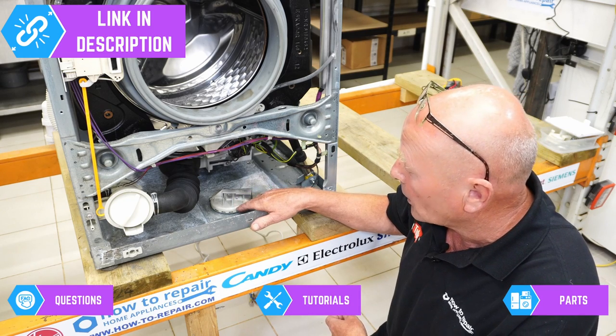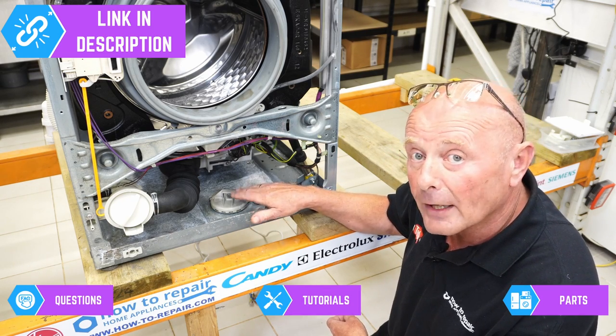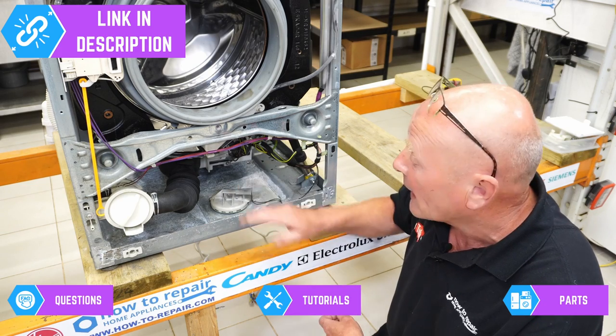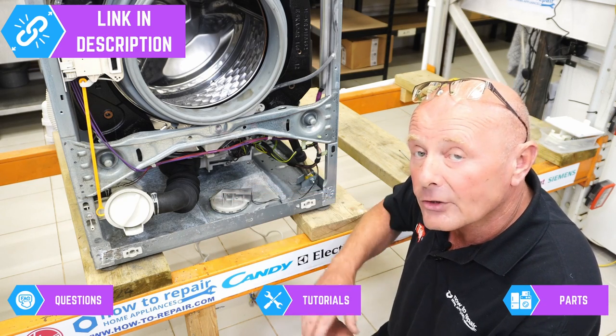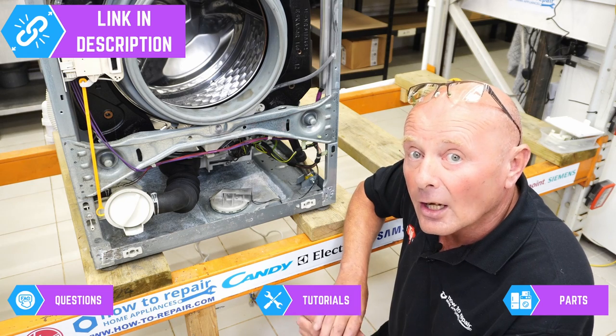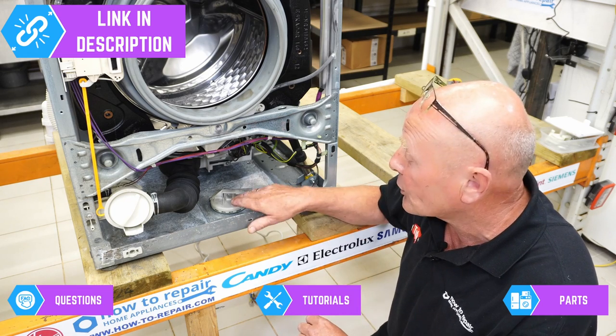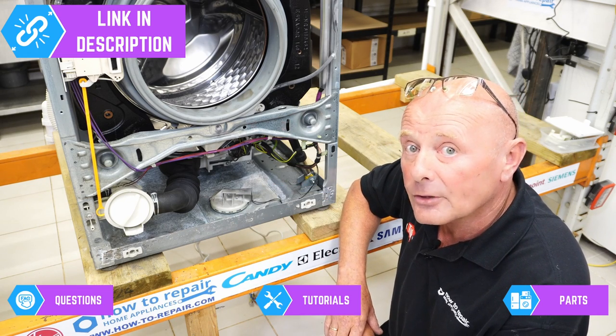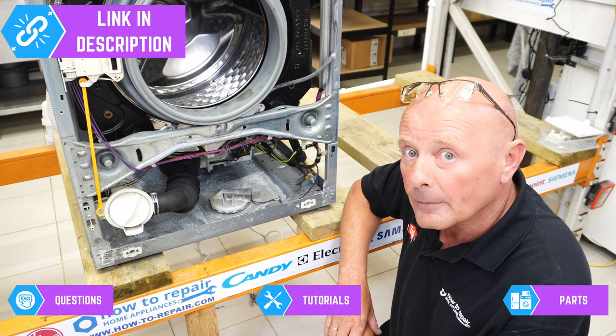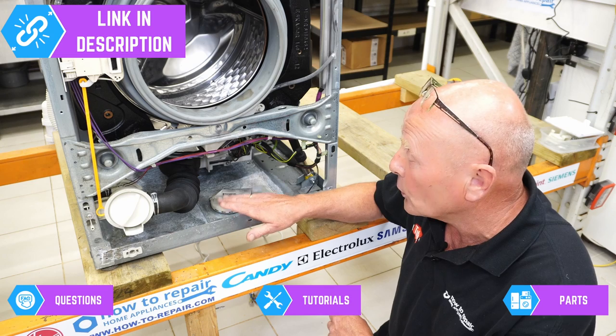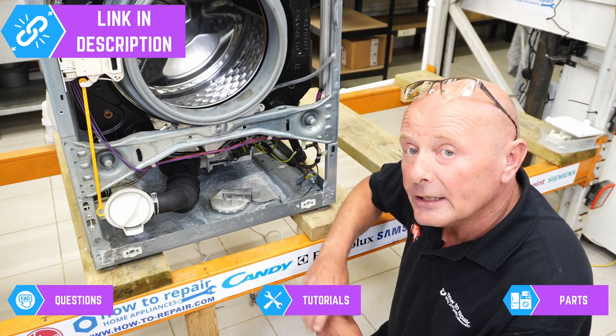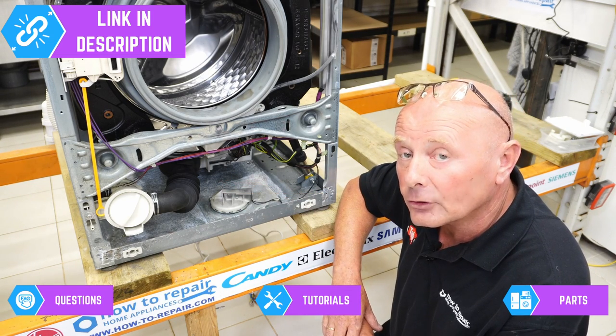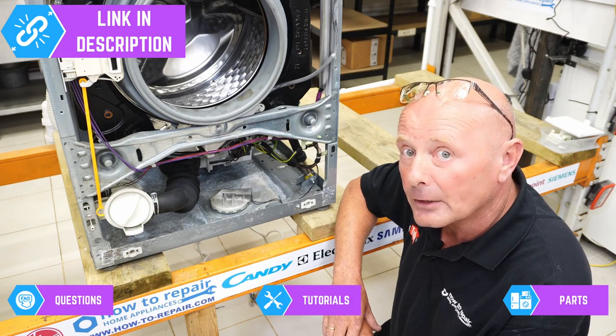This is a piece of polystyrene which attaches by a lever to a switch, and if the water level in the base of the machine ever exceeds a couple of millimeters, this switch is activated and the machine is put into a safety system mode, and then will show an error code. This is normally to do with a leak on the machine, and you would need to take the side panels off the machine to ascertain where the leak is coming from and then rectify the problem.